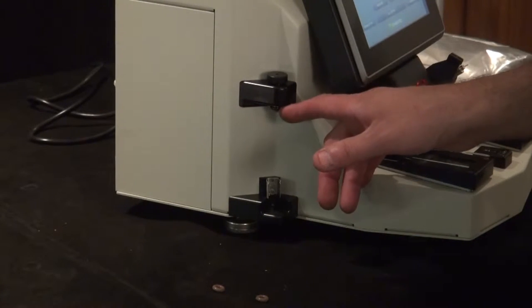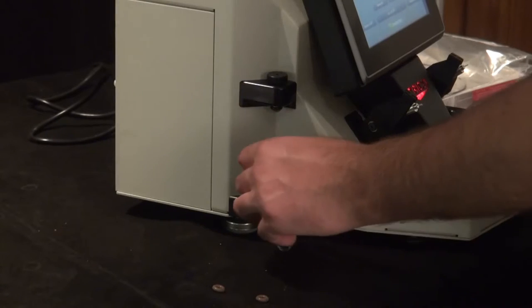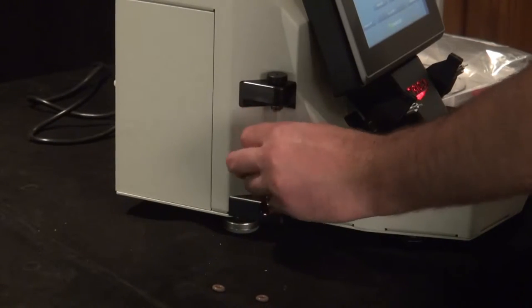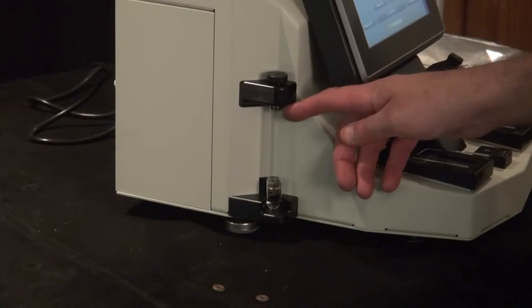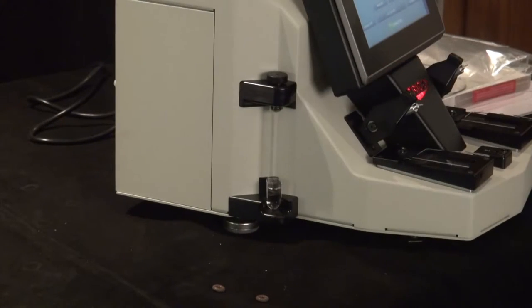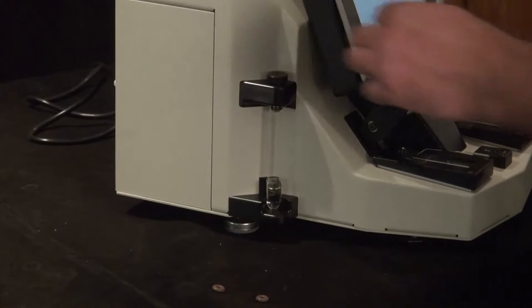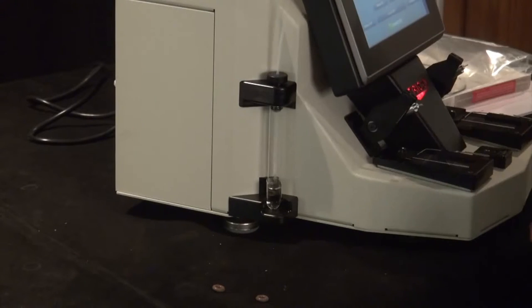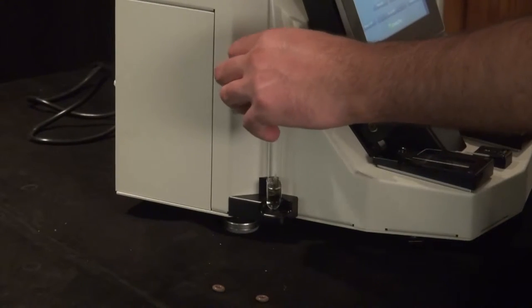The reason why you want to replace these is when you insert the vial repeatedly over and over again, it wears on the o-ring at the top. Same goes for the sample tube that goes into the unit through the top portion here. It slides past the o-ring, so that wears, and those are replaceable parts.